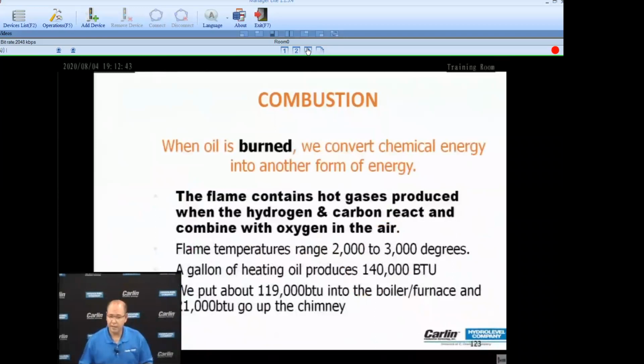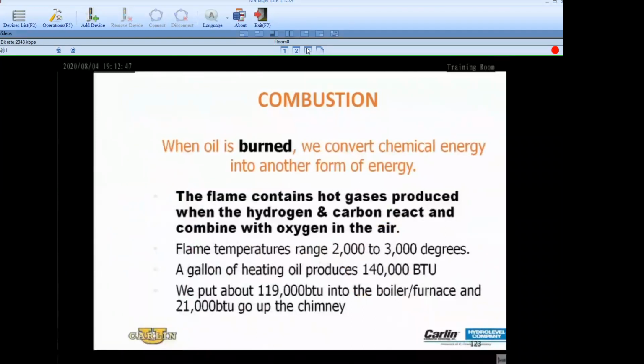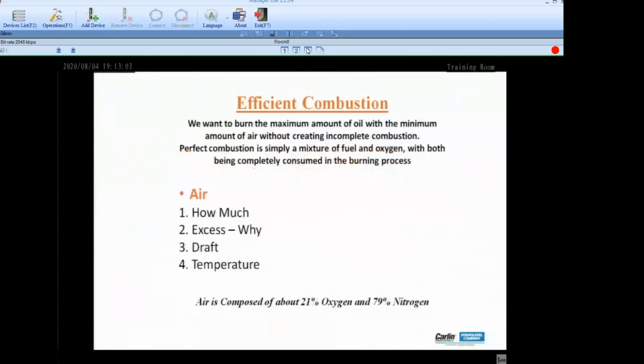Here again, flame temperatures, 2,000 to 3,000 degrees. Oil can generate 140,000 BTUs per gallon, assuming an efficiency somewhere around 85%. So we're putting 119,000 BTUs into that appliance. The other 21,000 is released up the chimney.